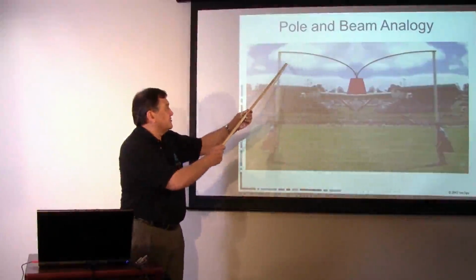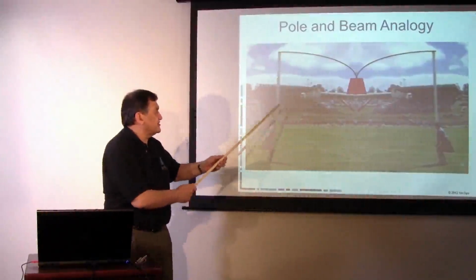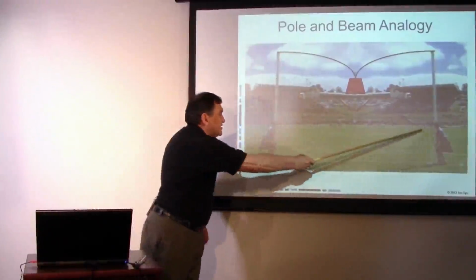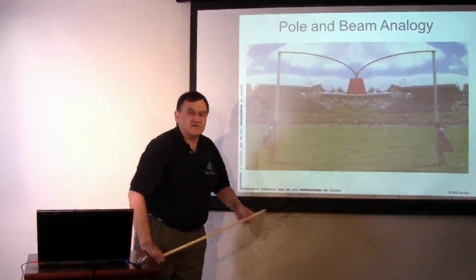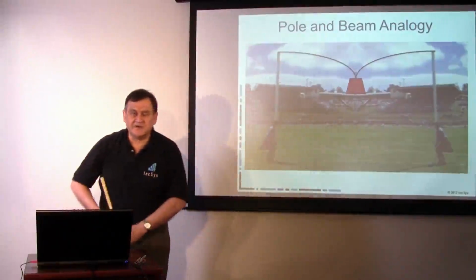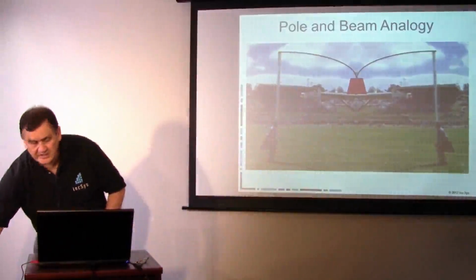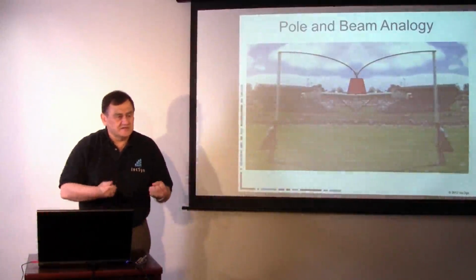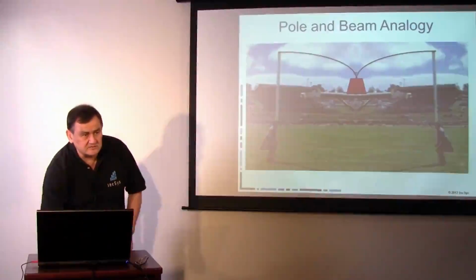In the pole analogy, as one cable lifter drops on down, think about what happens: if this guy comes all the way down, instead of sharing the load between this lifter and that lifter, this lifter will have the entire weight. So that's the impact: when one generator hits its megavar limit, the other generators have to pick up that load.